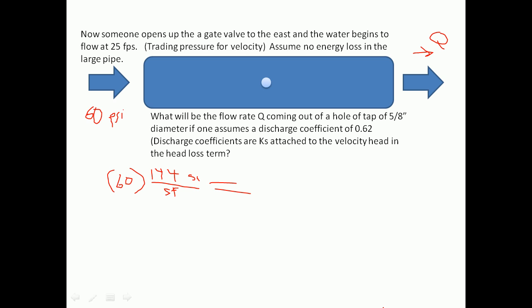So 60 PSI divided by 14.7 times 33.9. Again, you have 138.36 feet of head. That's what you had, 138.36, that's feet of head. Feet of head, which is foot-pounds of energy per pound of material.